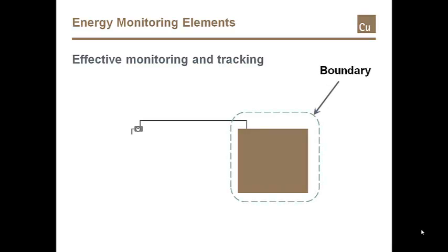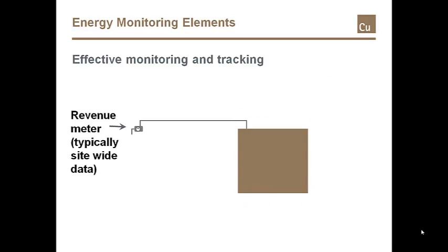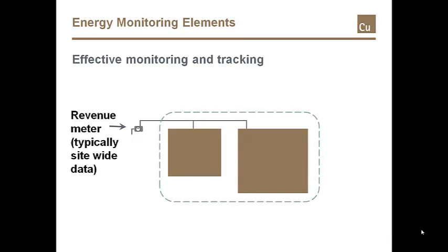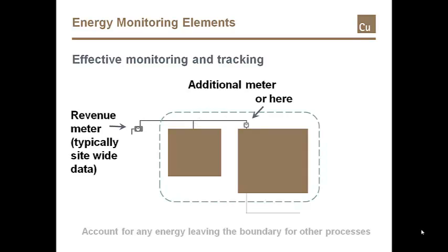All energy going into this boundary must be measured. Typically, energy measurement for the boundary involves one or more revenue meters. Additional meters may be necessary should several buildings fall within the boundary, so that the energy used may be effectively monitored and tracked. Energy passing through the defined boundary and going elsewhere must also be measured. Whatever the arrangement, the metering should allow an accurate accounting of actual energy used within the defined boundary.